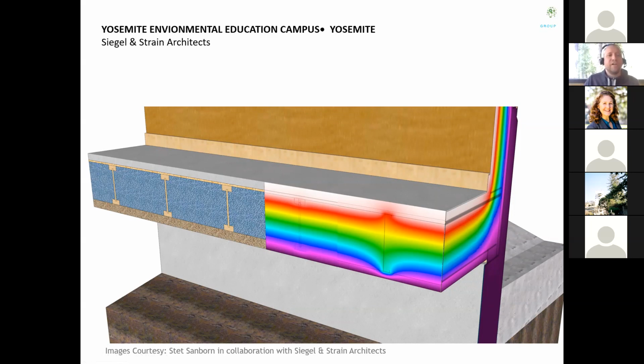For the saltwater question relative to the cooling coil, you have to use a coil that's titanium. It's designed to allow salt water to go through and then back into the ocean, so there really isn't too much environmental impact. The actual coil itself is designed for the salt water. The key is when the water goes back into the ocean, you can't take it to the same depth where the water's cold. You want to take it back up so it can be released at the temperature strata that the water is actually at, so you don't disrupt the ecology in the ocean.